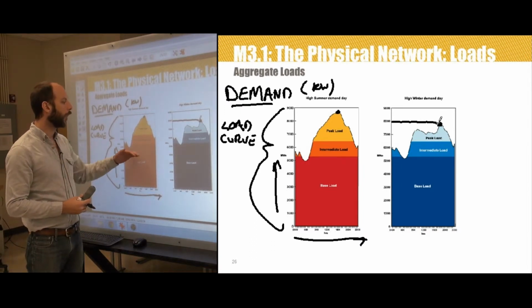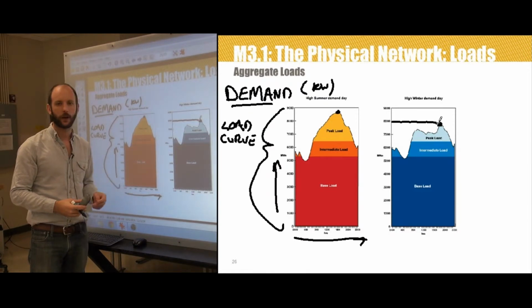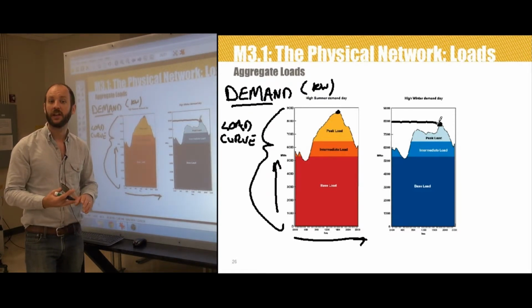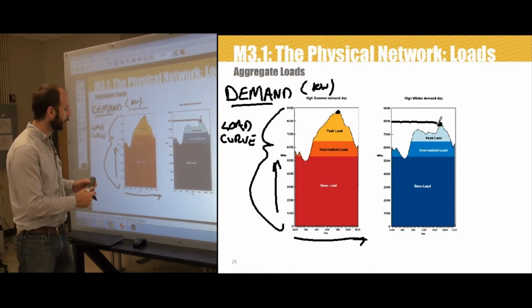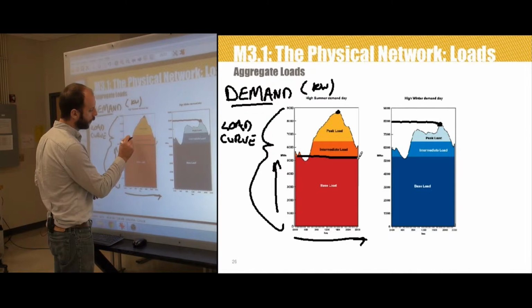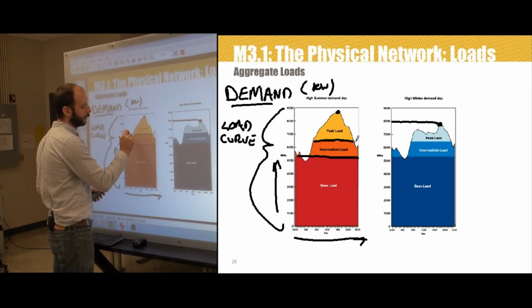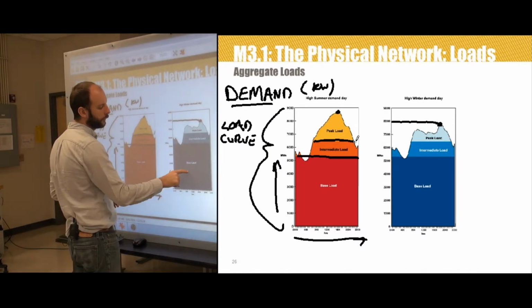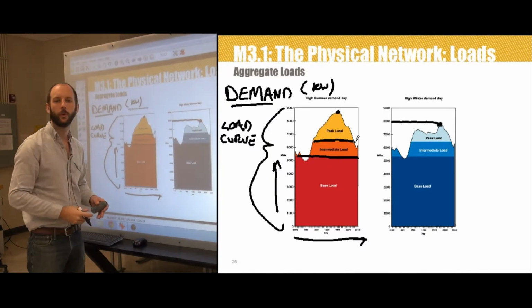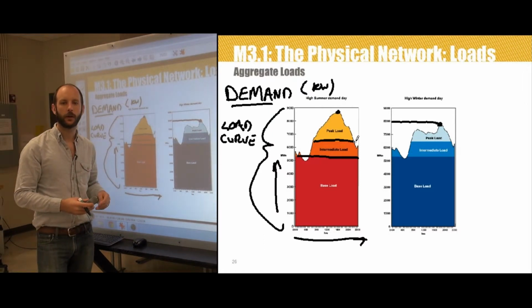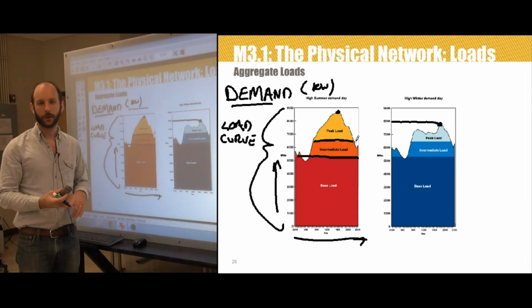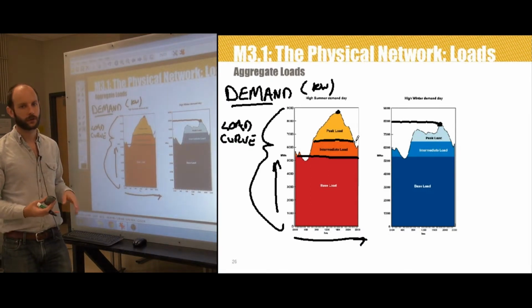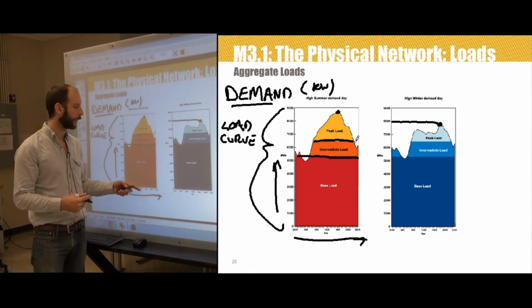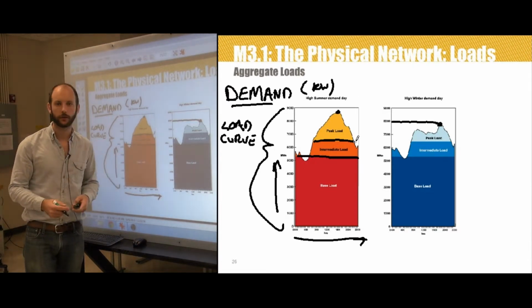So not only do we divide it between seasons, which is very common, we also take the demand during the course of the day and categorize it into base load, which is this dark red. The orange is called the intermediate load, and this yellowish color is called the peak load. You can see we've done the same thing, just using different colors, on the winter day. The reason this is done is primarily to determine the type and quantity of power plants that are going to be utilized to produce the electricity at the right times. Different power plants have different characteristics that are suitable for different operating scenarios, and we have to match those power plant characteristics with the power demand of the customers at any given time.